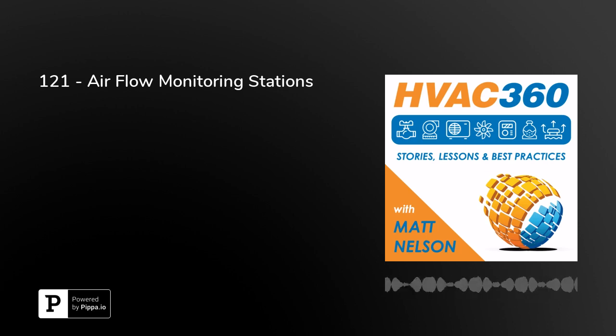Sometimes when you look at the supply airflow for different air handling units, it is just a sum of a bunch of little airflow monitoring stations on the VAV boxes themselves. They really just sum that up, and you can get the total of a unit that way. Another option, if you have more of a constant volume unit that doesn't have VAV boxes, is to put an airflow monitoring station in that. A lot of times it's not so much about the supply airflow though, it's more about the outside air. Engineers are usually more concerned about the airflow monitoring station of the outside air to make sure they're getting enough air in the system. So that's typically why they use them.